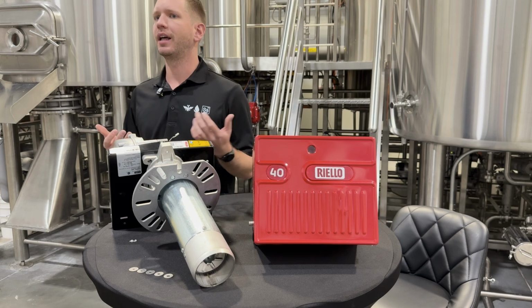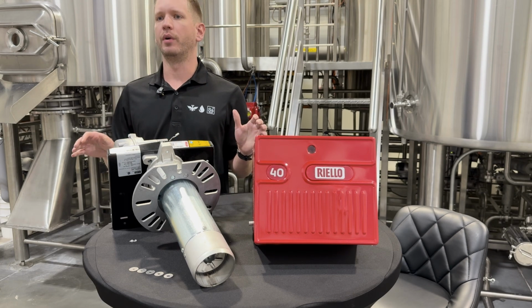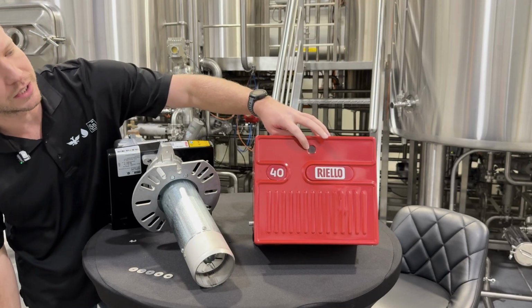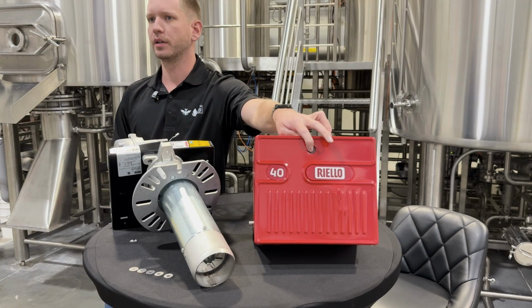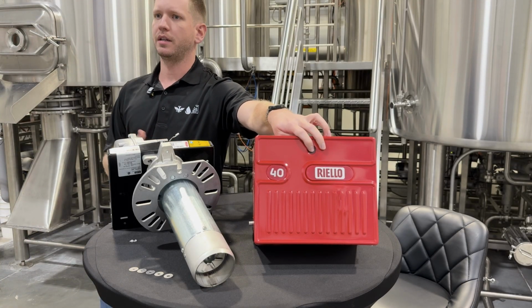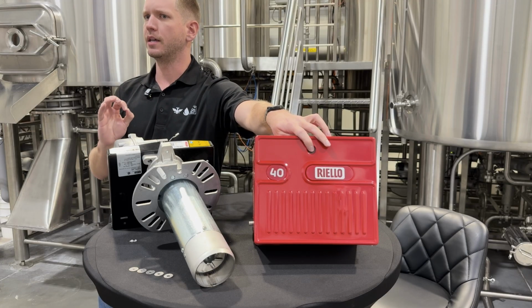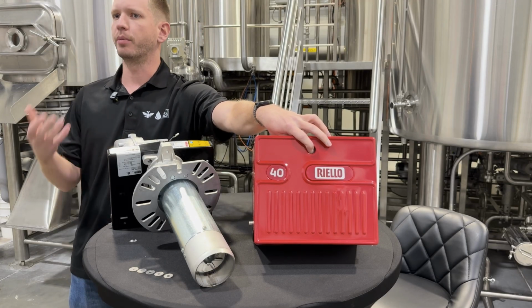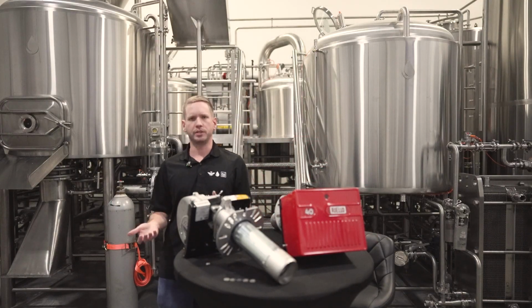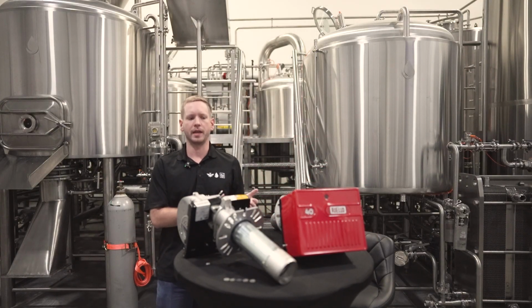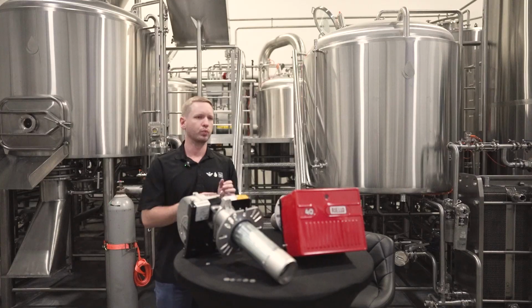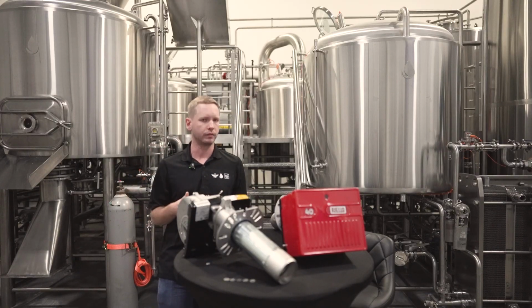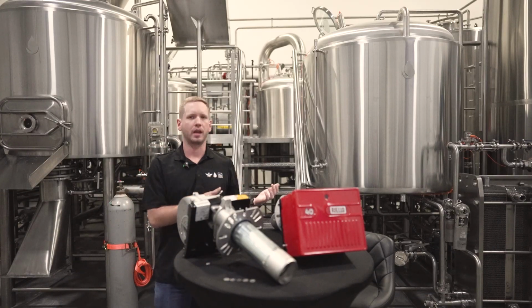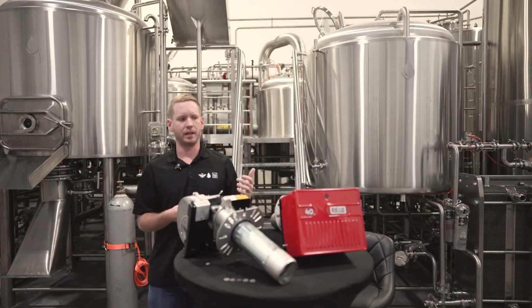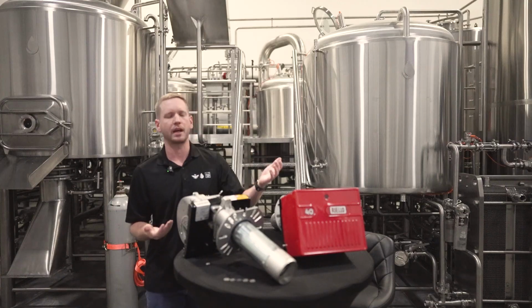If you feel as though it's an electrical issue, the first thing to do always is just smash this little reset button here. On the front end of every burner, you have a reset button. When it's plugged in, it'll have a little faint red dim to it. If you just press that, that'll reset your burner. We see that happen a lot if there are fluctuations in that main gas pressure. If your burner tech has hit that main header pressure right at the max set point this burner is looking for, it'll fall out of process, and it will trip the reset. So all you have to do there is hit that reset button.